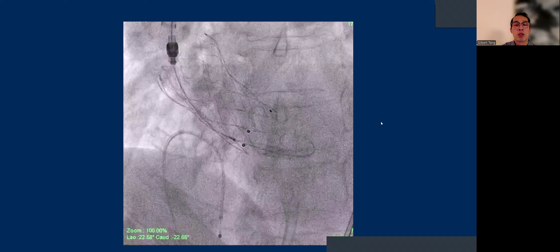So lately we've actually deployed and delivered the Flex Nav system with the flush port at 6 o'clock rather than 12 o'clock, based on manufacturer recommendation. So we basically flipped the catheter upside down, and we found that when you release the valve, because it's upside down, the tabs actually more easily release. You can see that here the 3 tabs simultaneously released. So there's no need to rotate the C-arm and also rotate the catheter to release the valve. So it's not perfect, but certainly we've seen that this is easier than if the flush port was at 12 o'clock. So I encourage you to give it a shot by having the catheter upside down.